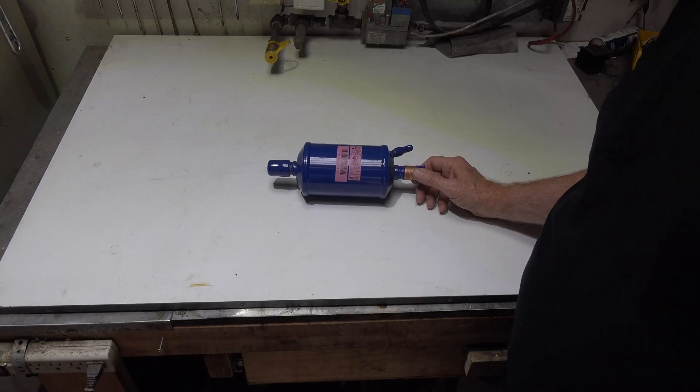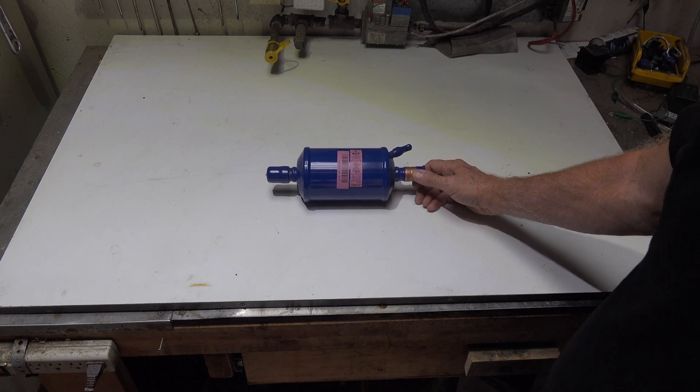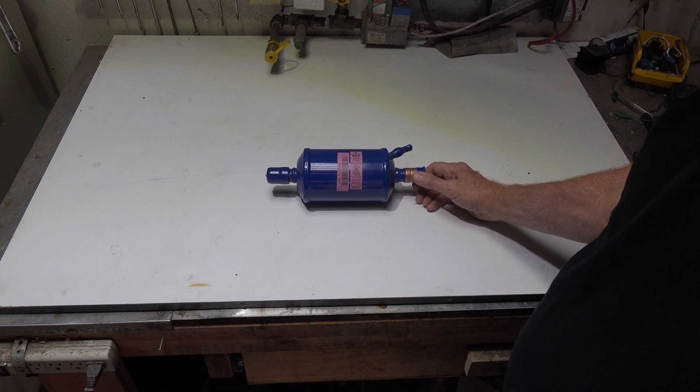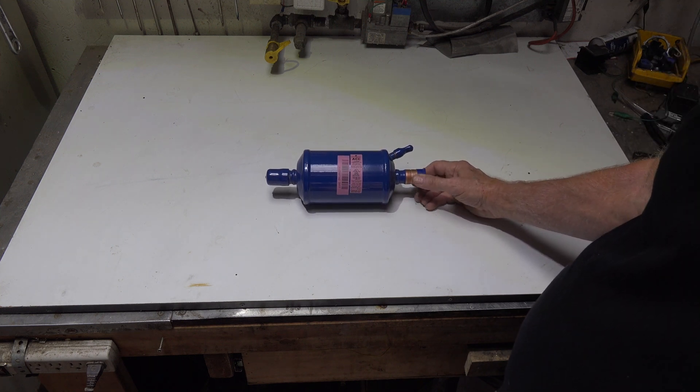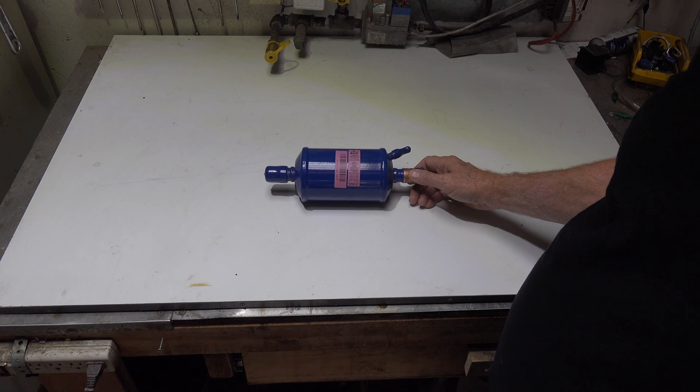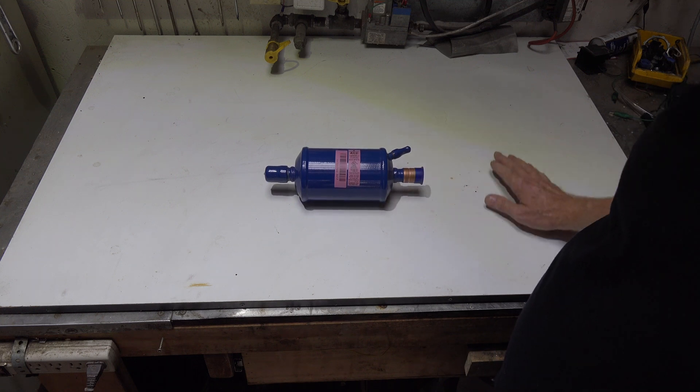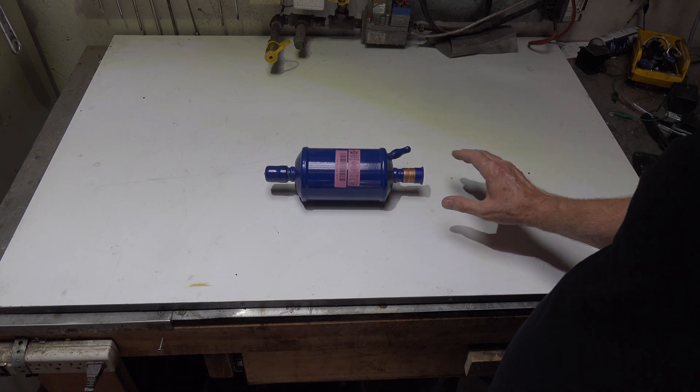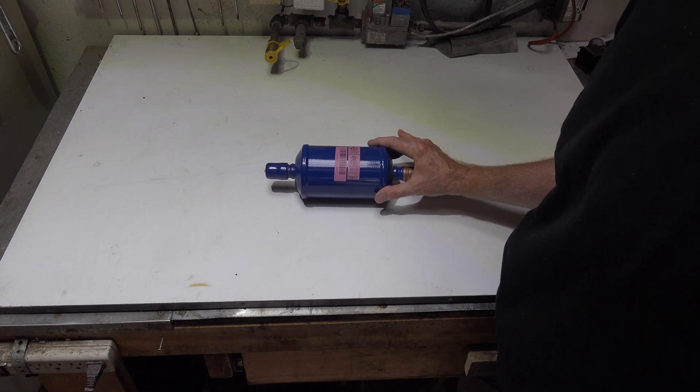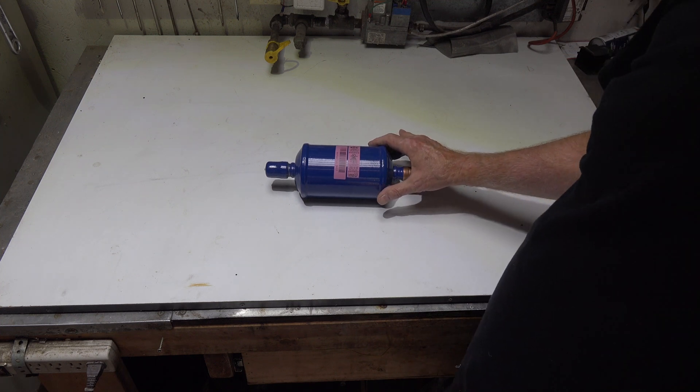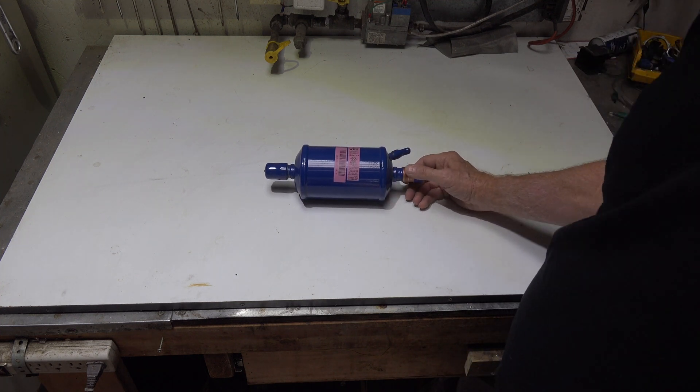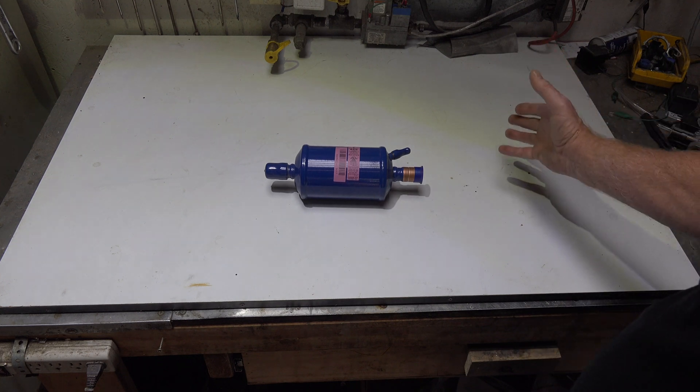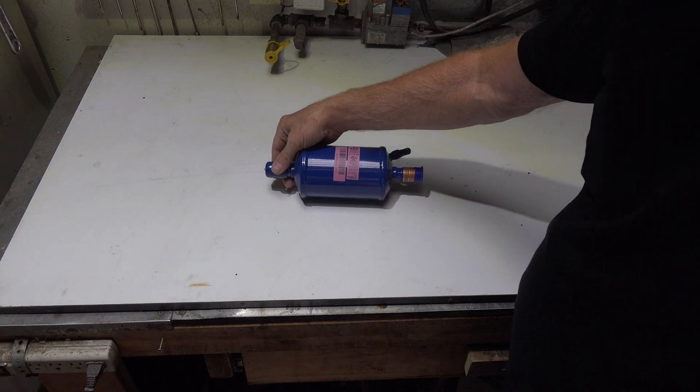Now this is a charge compensator. For the most part it actually looks like a suction line dryer, although it is listed here as a muffler. So UL listings for a muffler. Okay, this is a charge compensator.